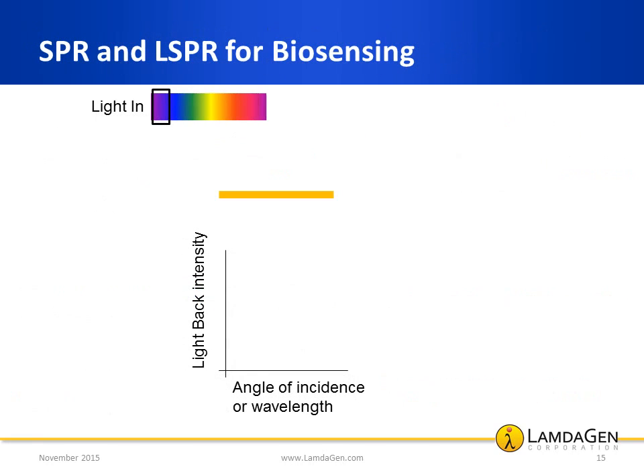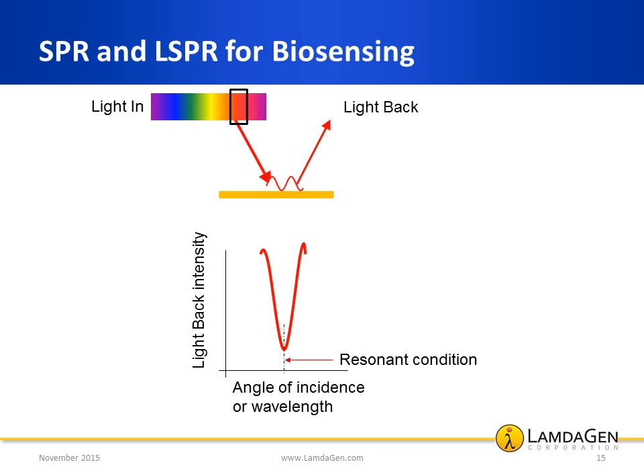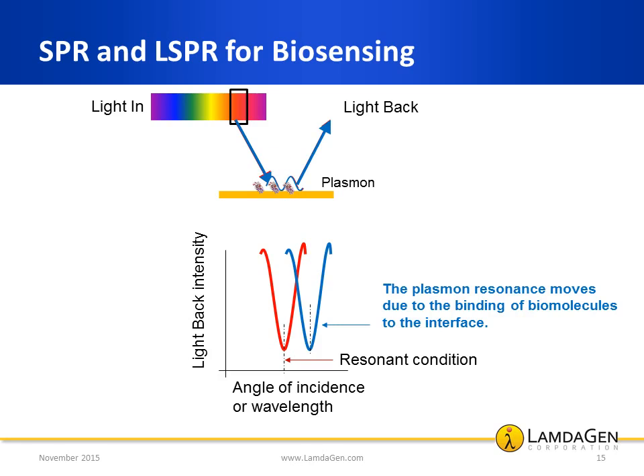Resonant conditions can be achieved by sending light onto the interface at a certain angle of incidence. If the resonant conditions are met, a surface plasmon is launched at the interface and results in a sharp decay of the reflected light. This can be accomplished by scanning the angle of incidence at a fixed wavelength or by using a broad light source with multiple wavelengths. The resonant conditions in both SPR and LSPR are very sensitive to the nature of the interface — if a thin layer of biomolecules is adsorbed onto the interface, the resonant conditions change. Even though the change may be very slight, it is measurable.